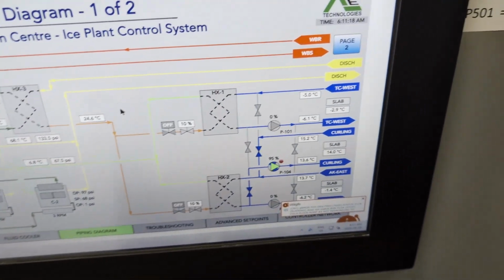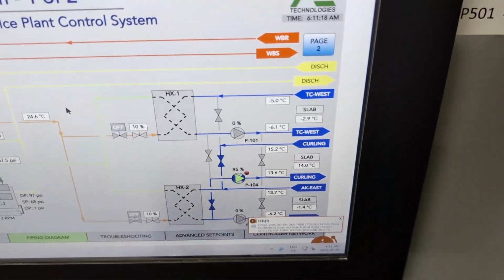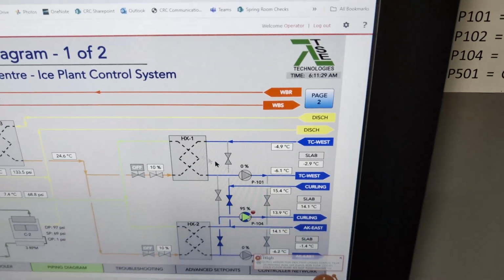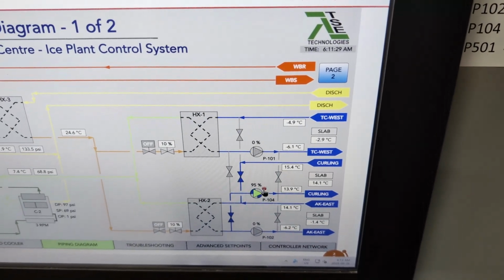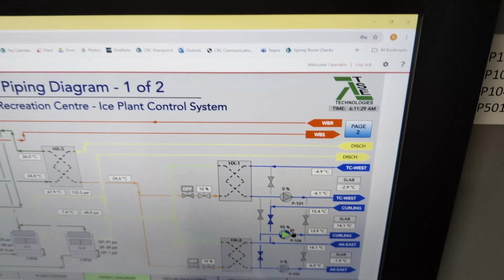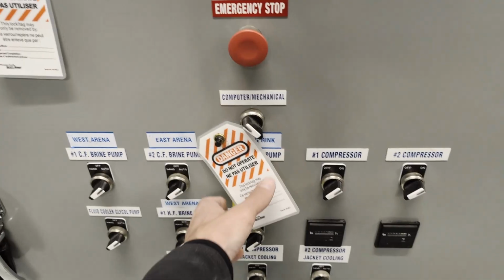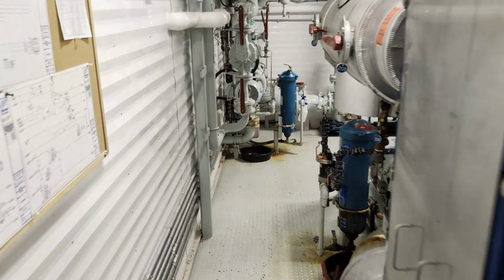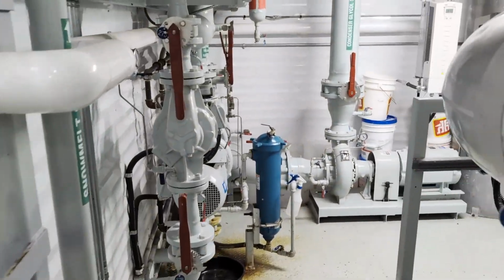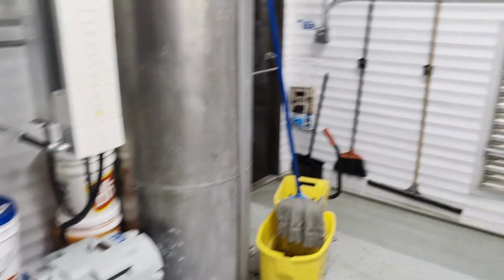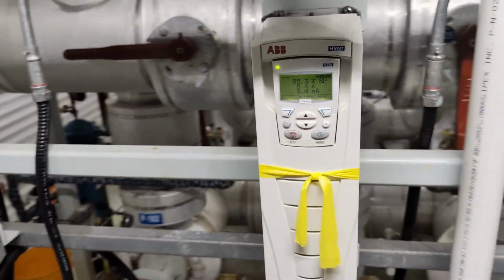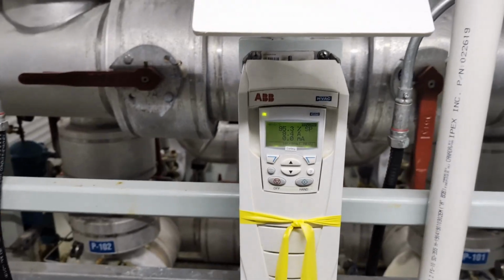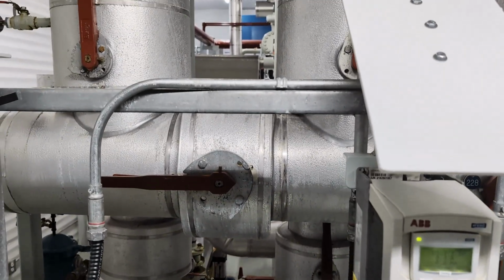And so you can see there's some alerts coming up, and that's just because it's saying that the pump's not listening to the computer, this little red dot, and that's because the computer is telling the pump not to run, and this is also telling the pump not to run, but the VFD is what controls the pump. So that's just a feedback command from the VFD to the computer, saying like, hey, this pump is running even though it's not being requested by the computer.